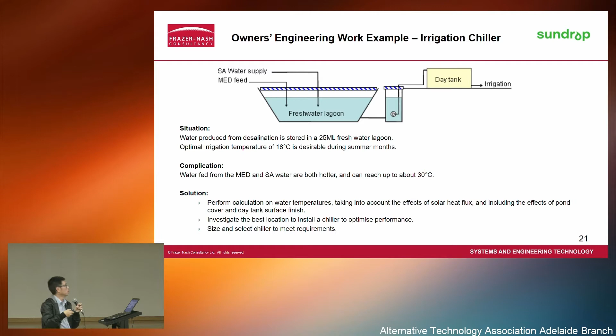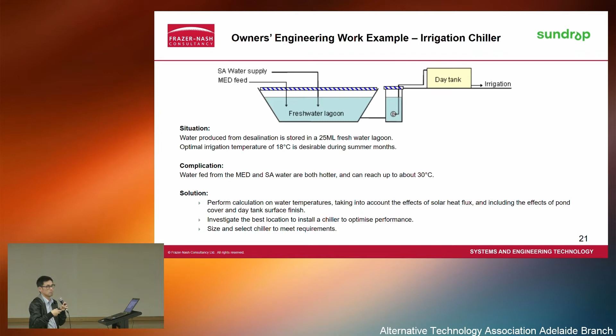The tank actually absorbs more energy when it's kept cool most of the day. So the compromise is: you can have a lower capacity chiller but use a bit more energy, or a high capacity chiller but use less energy chilling the water. The solution is that using the lower capacity chiller is actually much better - it also gives the opportunity to chill at different times of day, etc. That was the solution we derived.